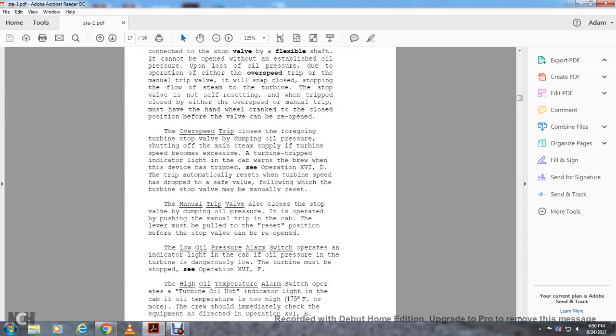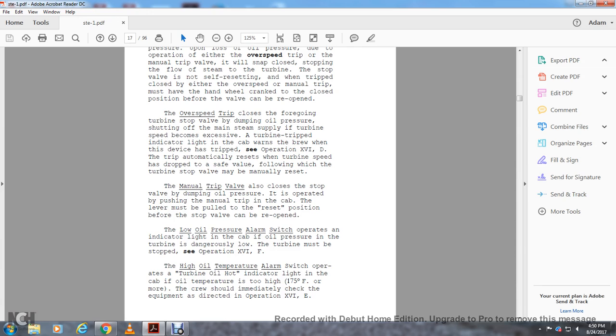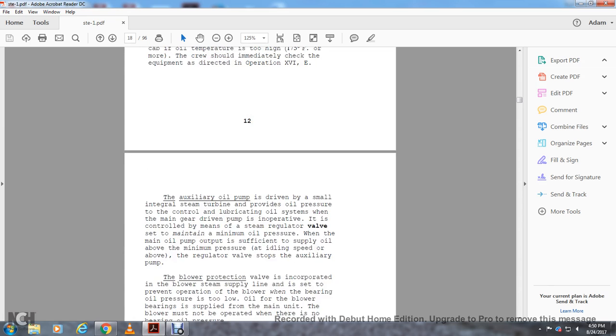The low oil pressure alarm switch operates the indicator light in the cab. If the oil pressure in the turbine is dangerously low, the turbine must be stopped. See operation number 16F. The high oil temperature alarm switch operates the turbine oil high indicator light in the cab. If the oil temperature is too high, 175 degrees or more, the crew should immediately check the equipment as described in operation 16E. The auxiliary oil pump is driven by a small integral steam turbine provided with oil pressure control of the lubricating oil system. When the main gear-driven pump is inoperative, the control means the steam regulator maintains the minimum oil pressure.